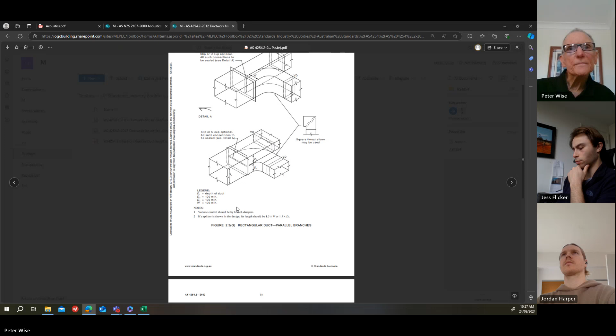Let's go back to the notes. Now, vibration. I mentioned that earlier. Vibration is quite tricky because you don't always know where it's coming from. It can be a major noise source in buildings. Vibration from a fan can be transmitted into ductwork and then into the building structure via the equipment or ductwork support systems. And this can create unwanted noise and vibration in an occupied space.